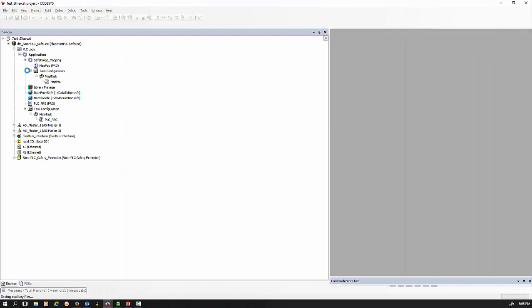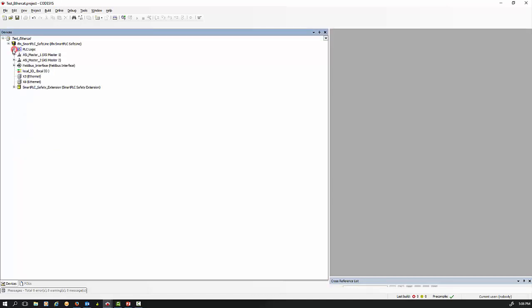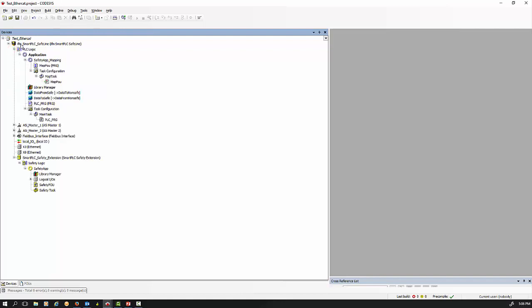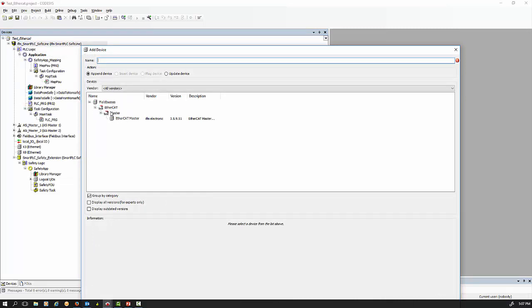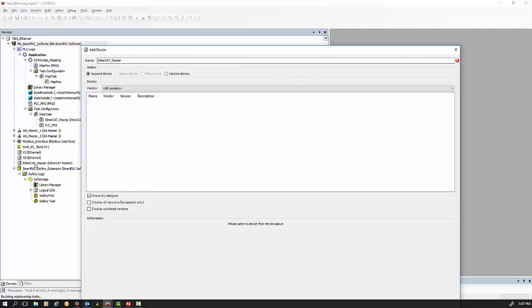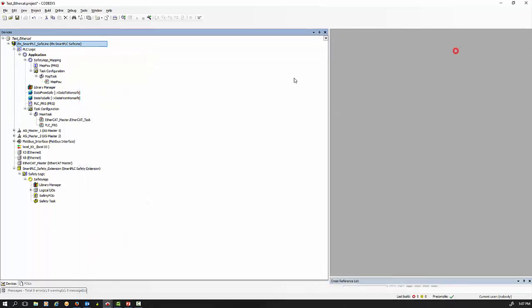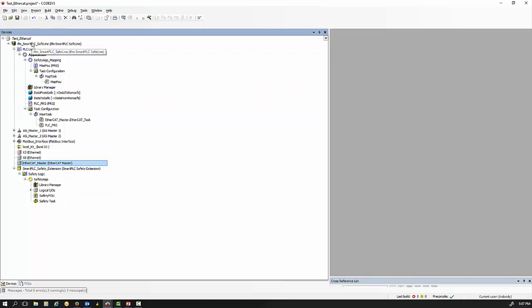This is your standard PLC and that'll be your safety PLC — it's a really easy system to add EtherCAT. You just right-click on your main PLC and say 'add device', which brings up different field buses including the EtherCAT master. Add the EtherCAT master, and you'll notice it adds it at the very bottom of your device tree on your non-safe PLC. From there you would have to select which port — this controller has port X3 and X8 on the unit itself.